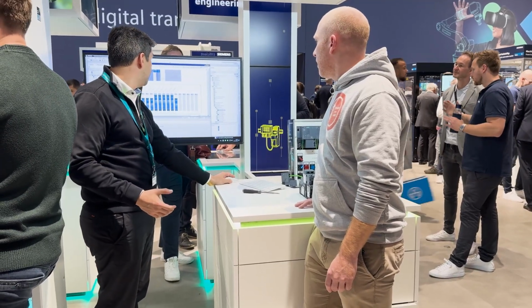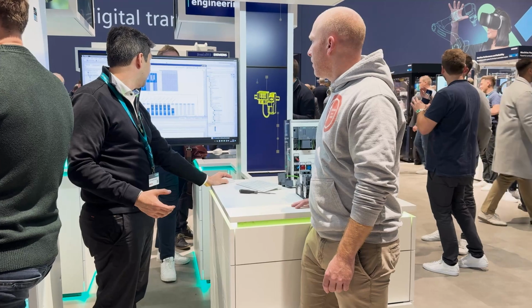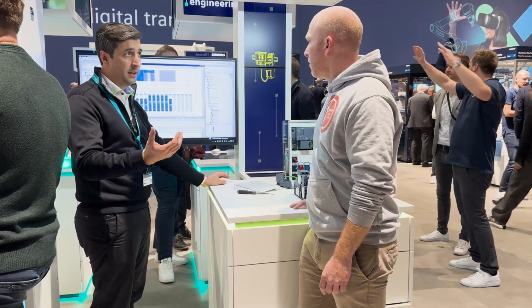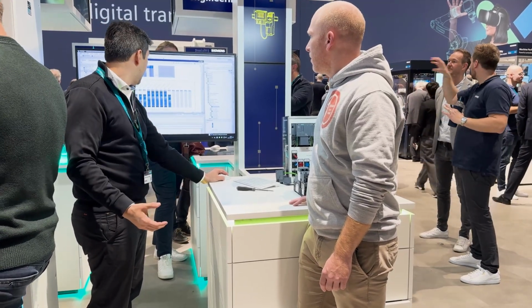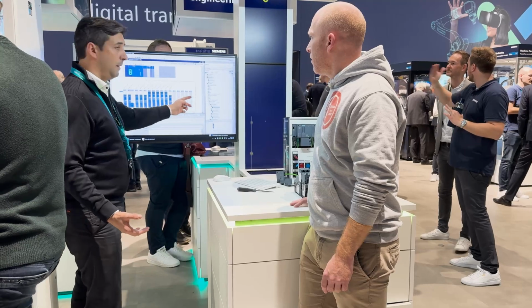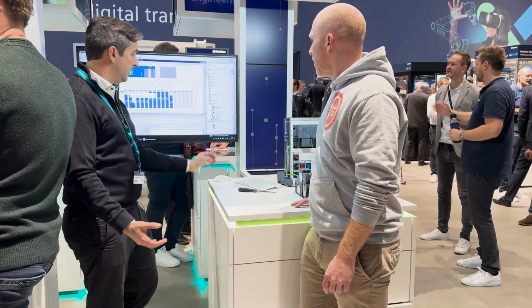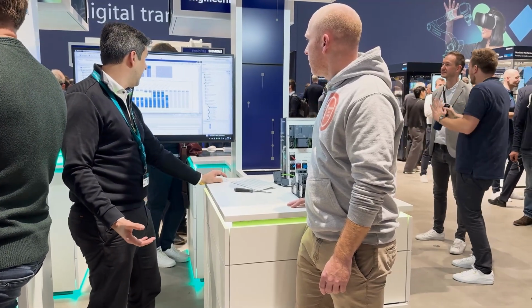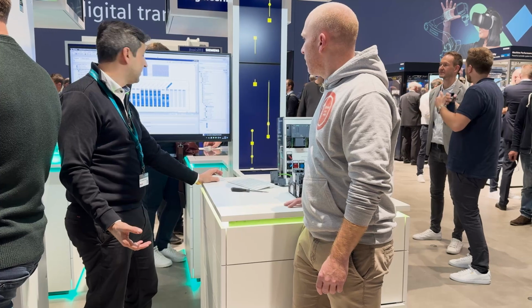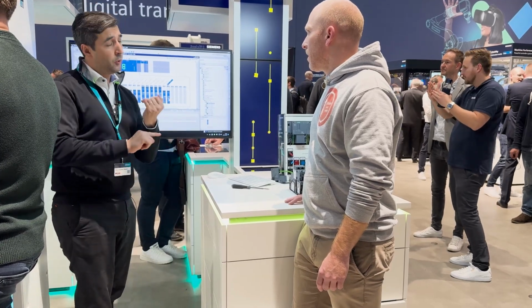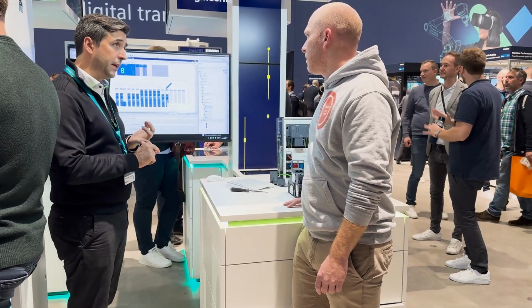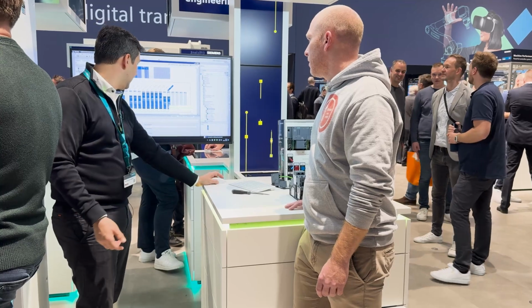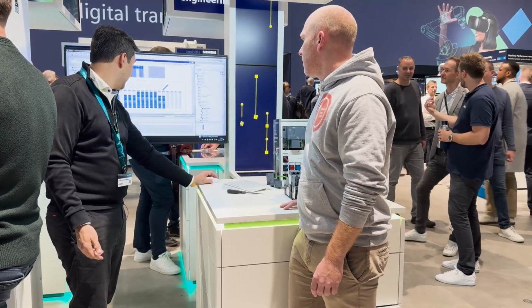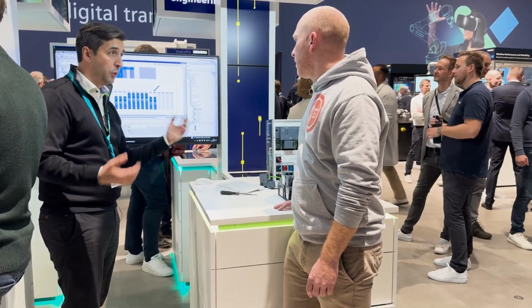You just have to set the extension rack that you already set here on the PLC or in the extension, on the ET200SP extension. And this creates a new rack where you can set up to 16 devices, and you just drag and drop the device. This drag and drop creates the communication, it also creates the diagnostics with the PLC, and the only thing that you have to do after that is basically just set the current range that you want to work with.